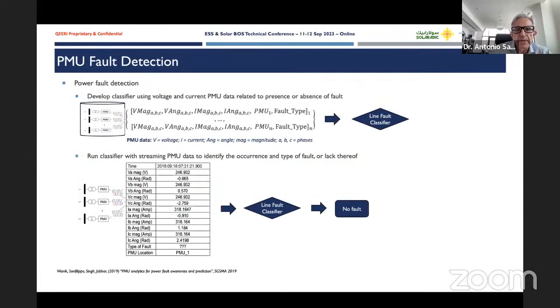So I want to give you a very quick example of how we do this. We collect data using phasor measurement units. We have this data collected from previous historical data, which consists basically of the measurements, voltage, current, angle and magnitude for all phases, and whether they're associated with a fault or not. So basically you use this data to develop a classifier, which you can then run in real time with streaming data to understand whether a particular set of measurements is indicative of a fault happening or not.